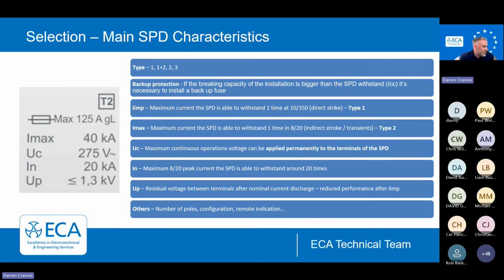In, this is on a type 2 device, and a type 2 device can take around about a 20 kA condition or fault around about 20 times. We say around about 20 times, that's what the product standard says, but there's no sort of ticker tape on this. It's not like it's got a little counting clock next to it. We don't know if that's had 12, 22, 18. We say around about 20. So it can take a little bit of impact quite often, up to about 20 times. Once these are done, they're done.